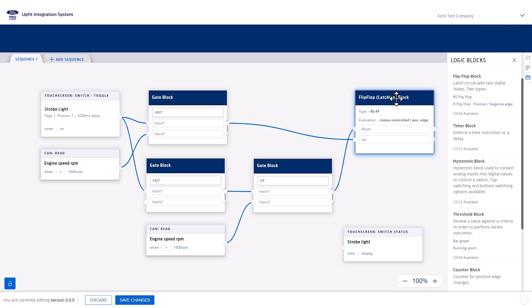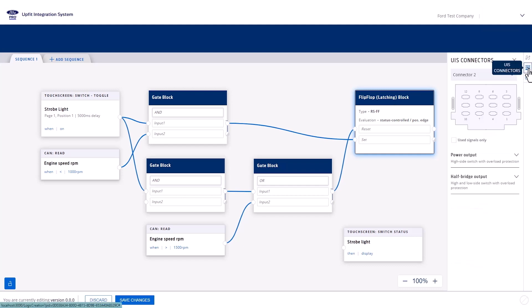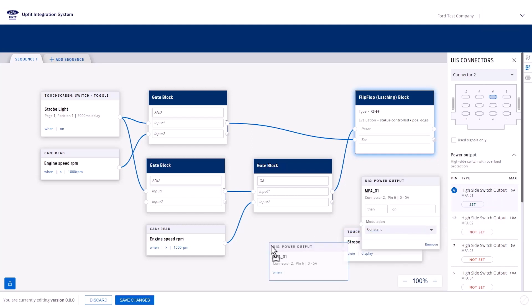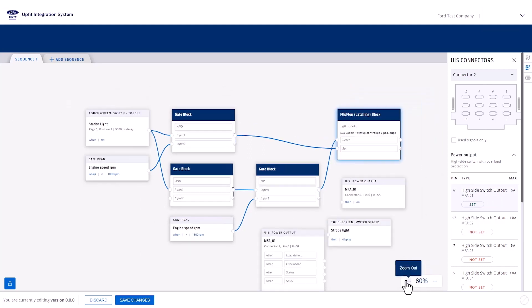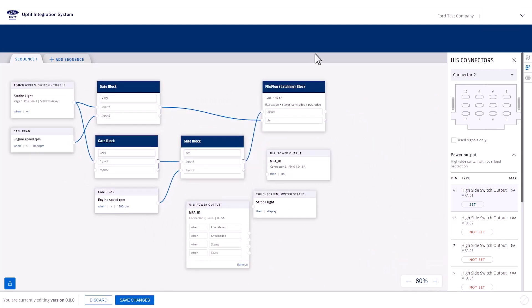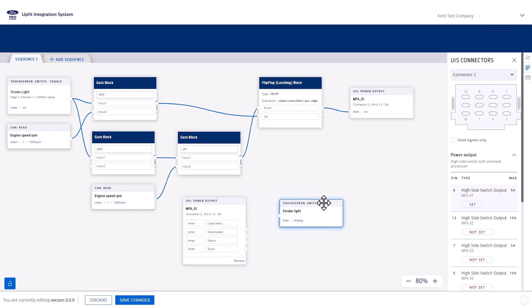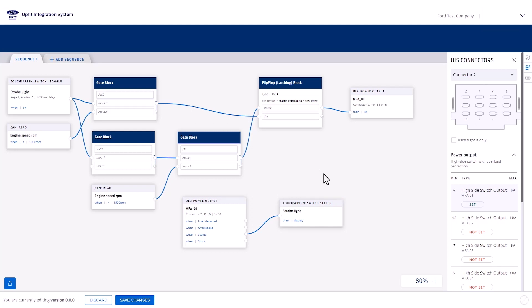Next, we need the power output block that represents the pin wired to our strobe light. Navigate to the right-hand panel and open the Connectors tab. Expand the power output section and drag two instances of the power output block to the canvas — the one that we wired the strobe light to. Zoom out to get a better view. Connect the flip-flop to the first strobe light power output block. Finally, connect the status node of the power output block to the touchscreen strobe light status block, so whenever the status of the power output pin changes, it will be reflected on the touch screen.